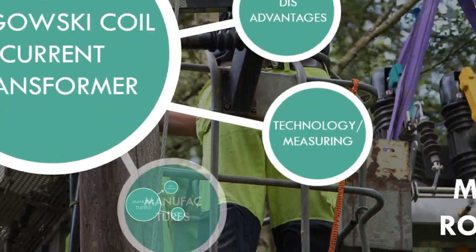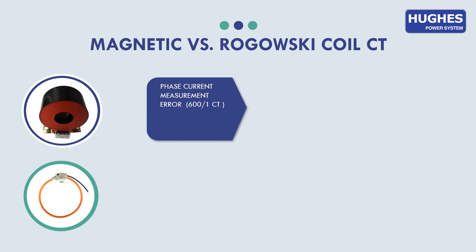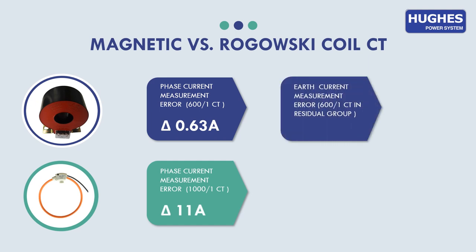Here you can see the results of the actual measurement performed in order to evaluate the measurement errors for both types. As you can see for magnetic current transformer, the phase current measurement error 600 to 1 CT was only 0.63 ampere. When in case of Rogowski coil, it was 11 ampere. Next is earth current measurement error 600 to 1 CT in residual group. For magnetic current transformer it was 0.1 ampere, and in case of Rogowski coil it was 2 ampere. This factor is very important, especially for isolated neutral type of network as almost 90% of the faults are below 2 ampere.